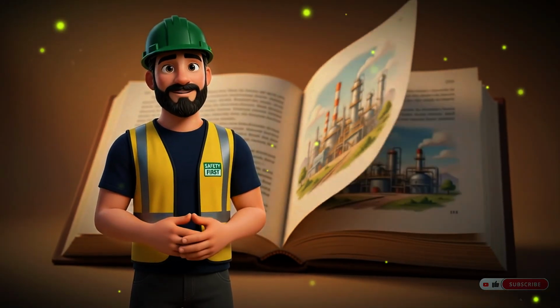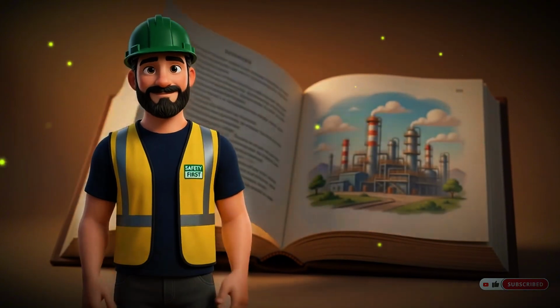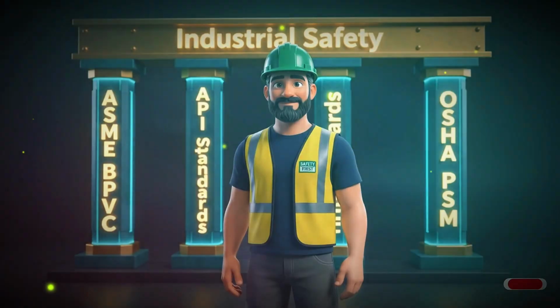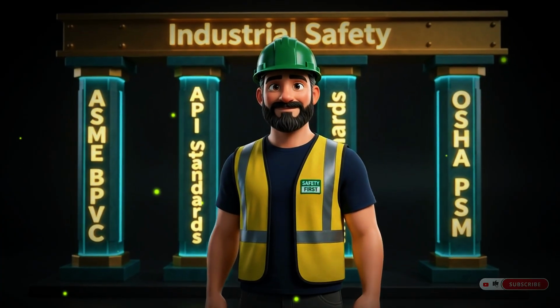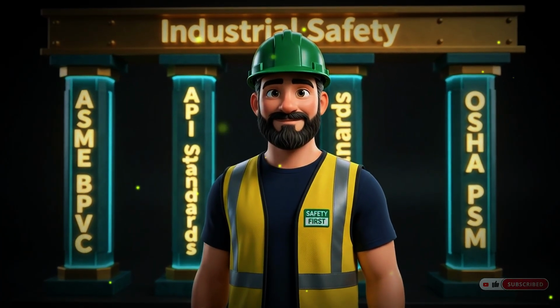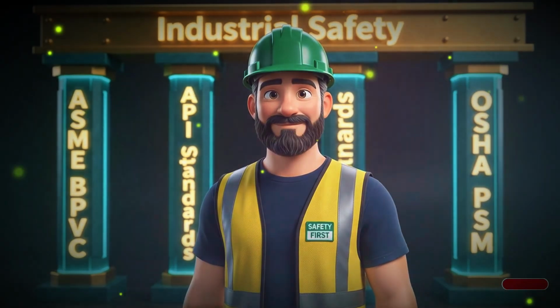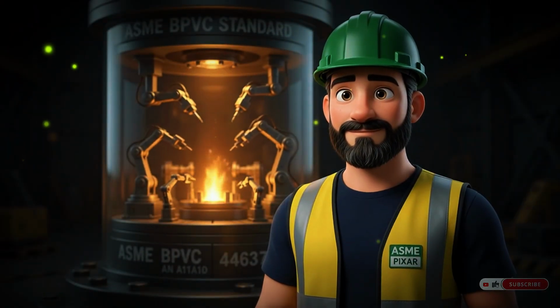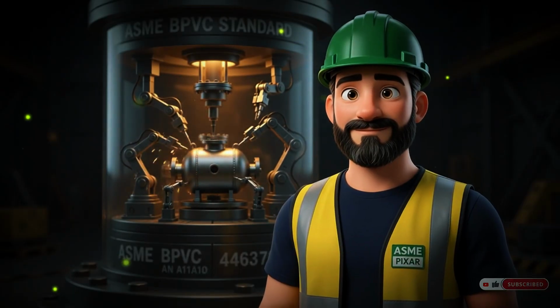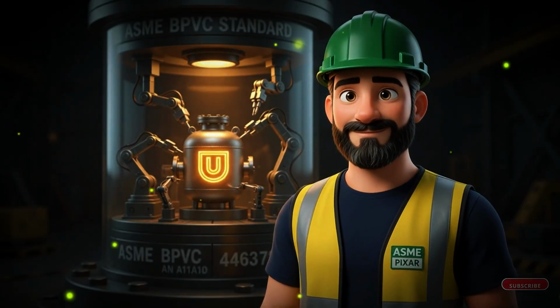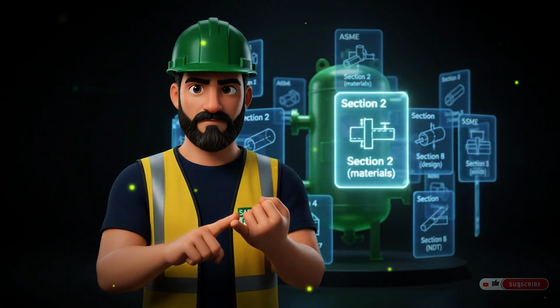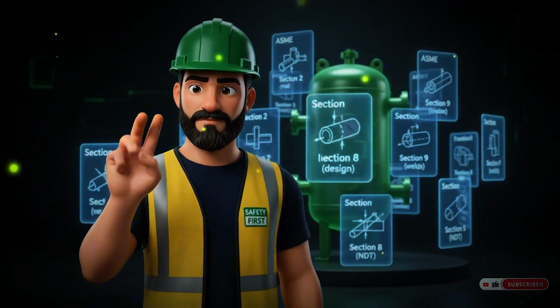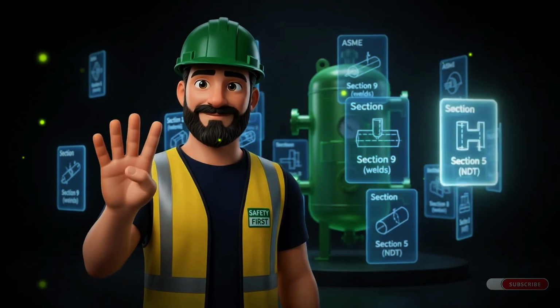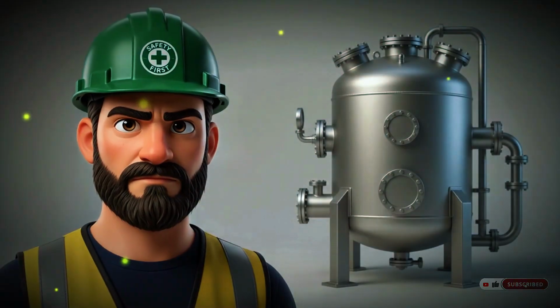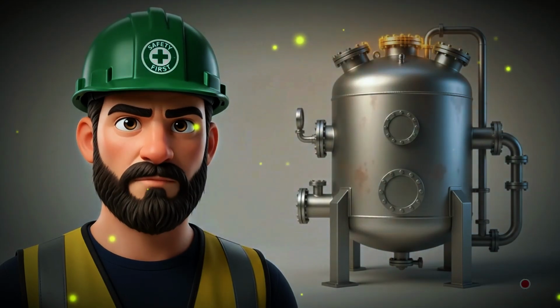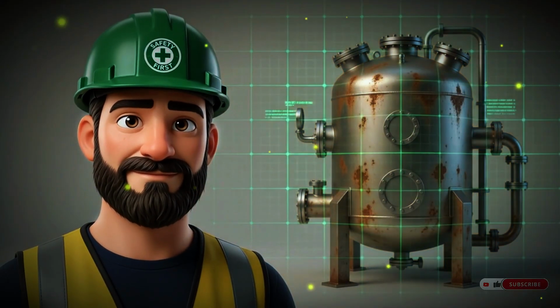I want to close this video with something that will be very useful for anyone working in the industry or studying to enter it: how these standards relate to each other and why none of them, alone, is sufficient. The ASME BPVC, the Boiler and Pressure Vessel Code, governs design and fabrication. When a pressure vessel leaves the factory with the ASME U stamp, it means the design was calculated according to the formulas in Section 8. The materials used were certified under Section 2, the welds were performed by qualified welders per Section 9, and the equipment passed the non-destructive examinations required by Section 5. The code guarantees the equipment was born right.